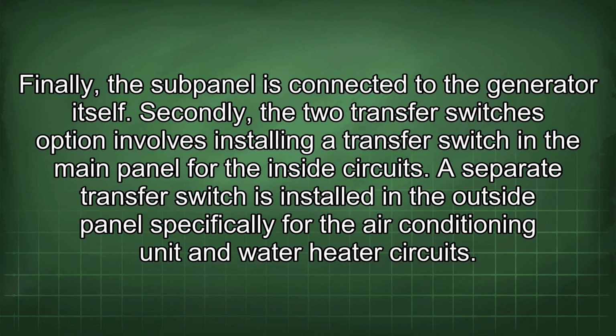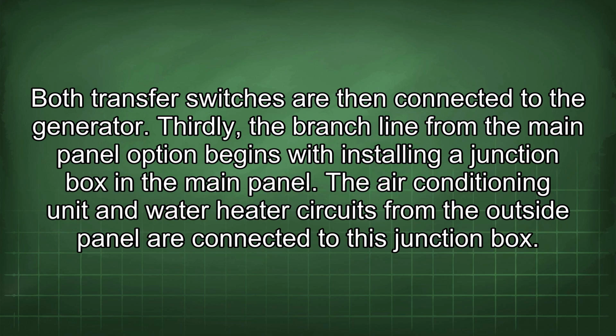Secondly, the two transfer switches option involves installing a transfer switch in the main panel for the inside circuits. A separate transfer switch is installed in the outside panel specifically for the air conditioning unit and water heater circuits. Both transfer switches are then connected to the generator.